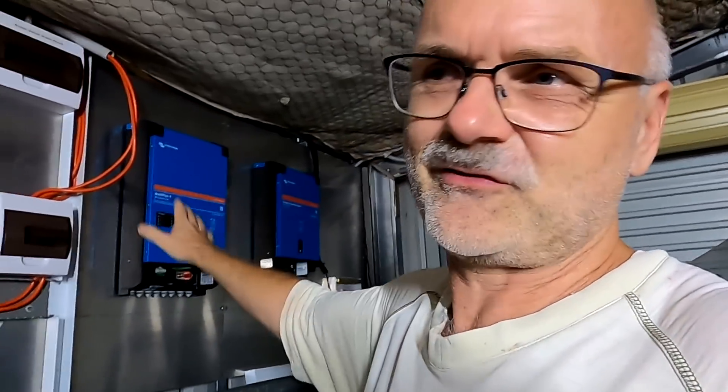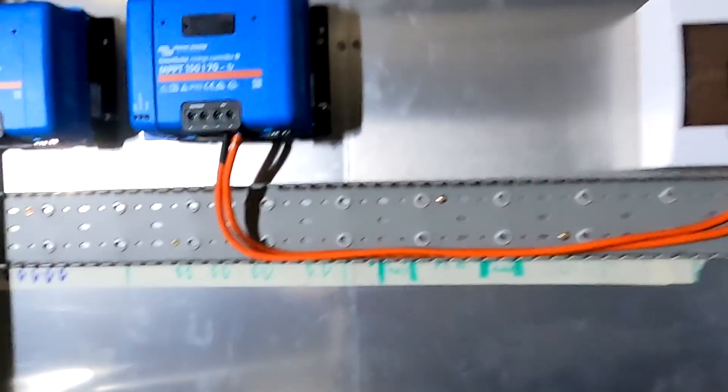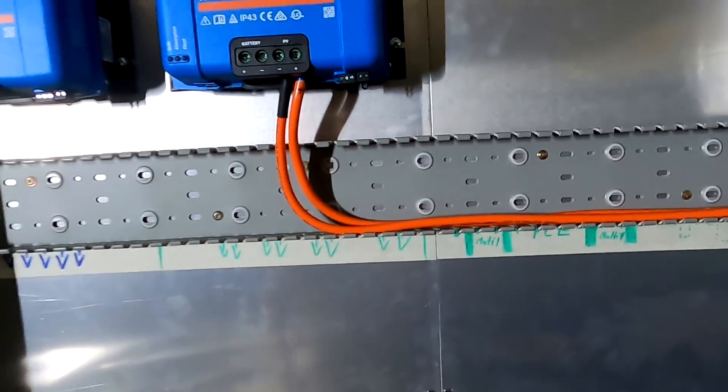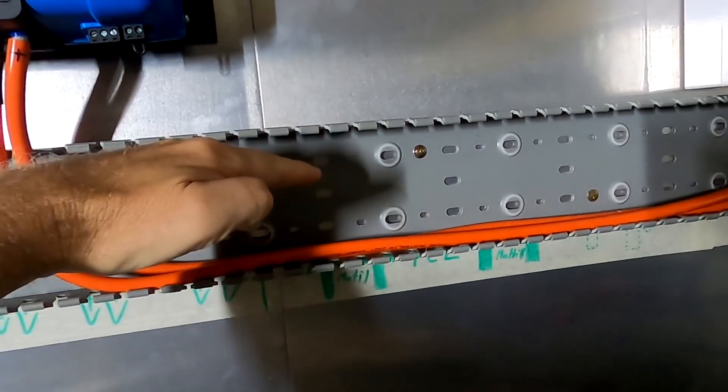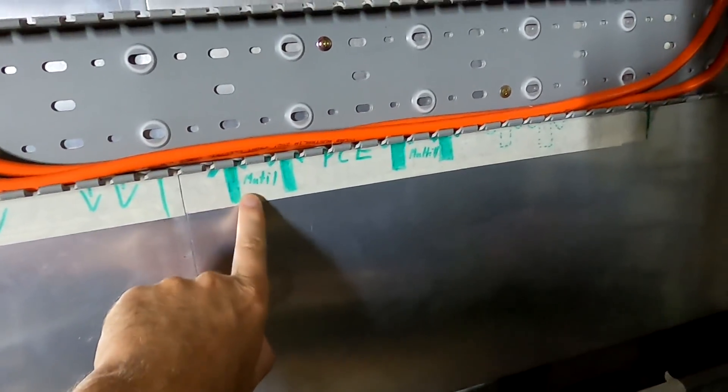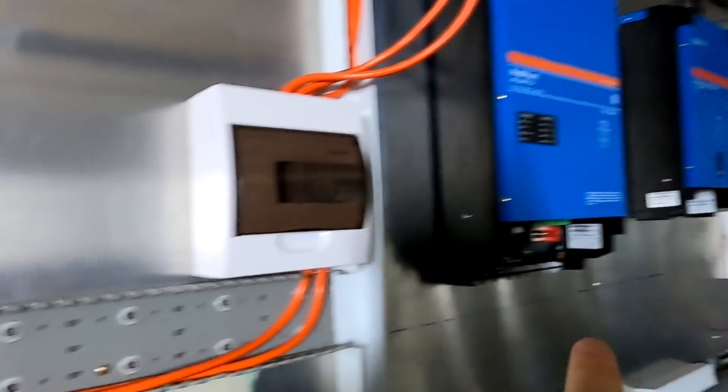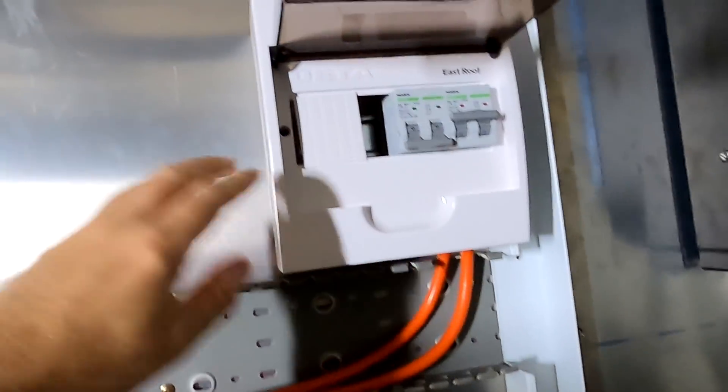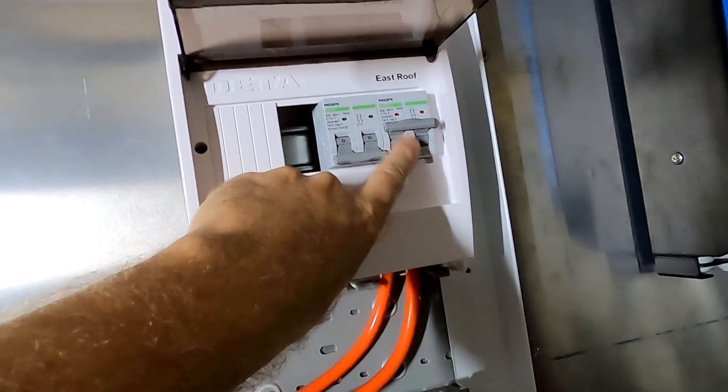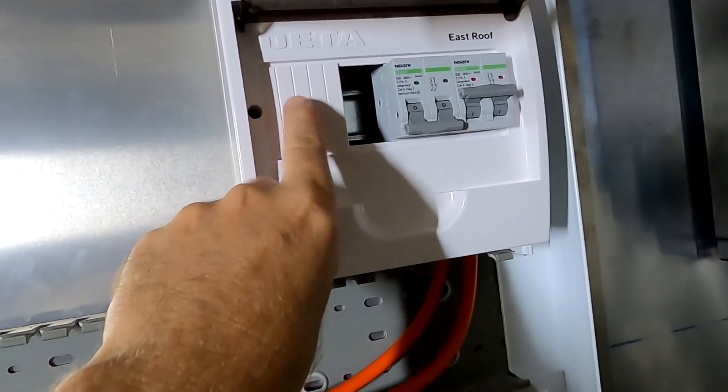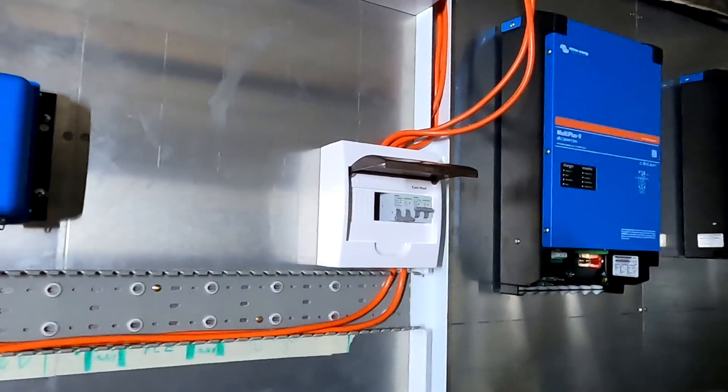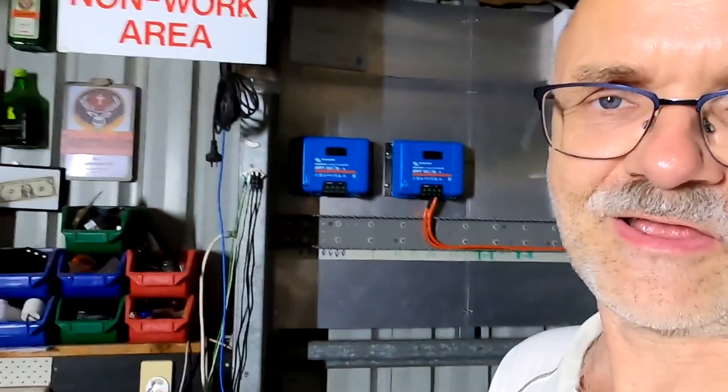But then this morning I said, Andy, don't focus on the AC side here at the moment. This is all clear. It just needs to get done. Focus more here on the DC side. And as you can see here, this cable is already far too long. I wasn't quite sure on which height it comes. So I left it a bit longer, but now it bites me back. Yeah, I have to cut them off a little bit. So this whole cable moves up because we need the space underneath here for the big 70 millimeter cables for both inverters. And then I really want to connect the second charge controller as well to charge our battery here. So east roof is already there and this breaker for the west roof goes a bit to the left here and then there will be another SPD here for the west roof. I still haven't made up my mind how to cable these SPDs, but I will make space in this switchboard here to actually put them in. And then we take care about the cabling later on if I have more information about how to do it correctly. Okay, so let's shorten these cables first and get this one connected. This would be my task for tonight.